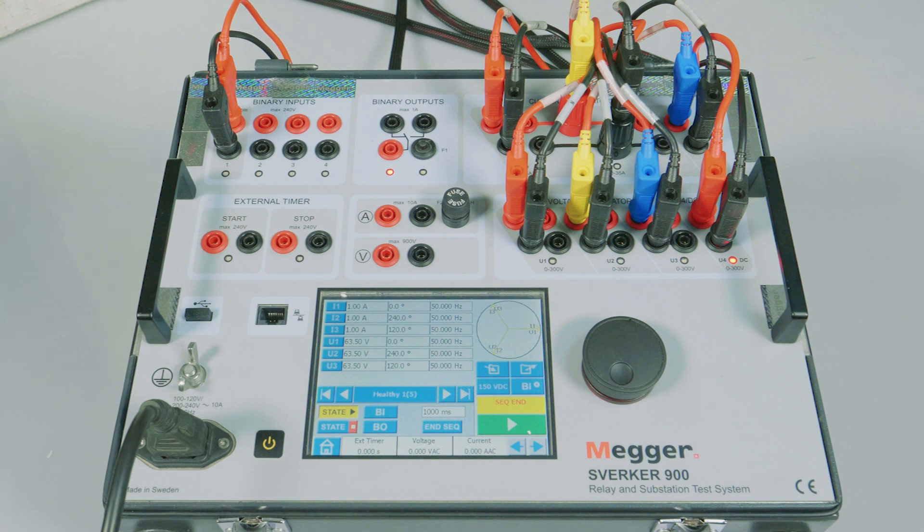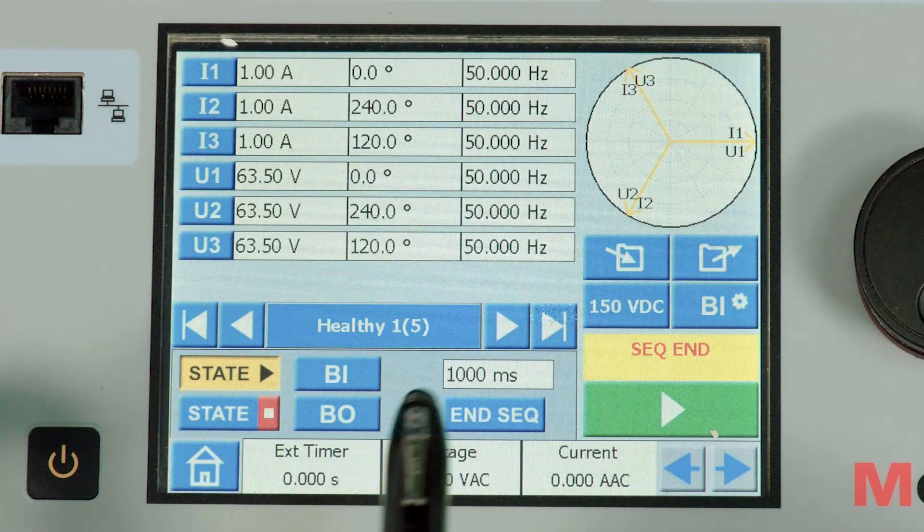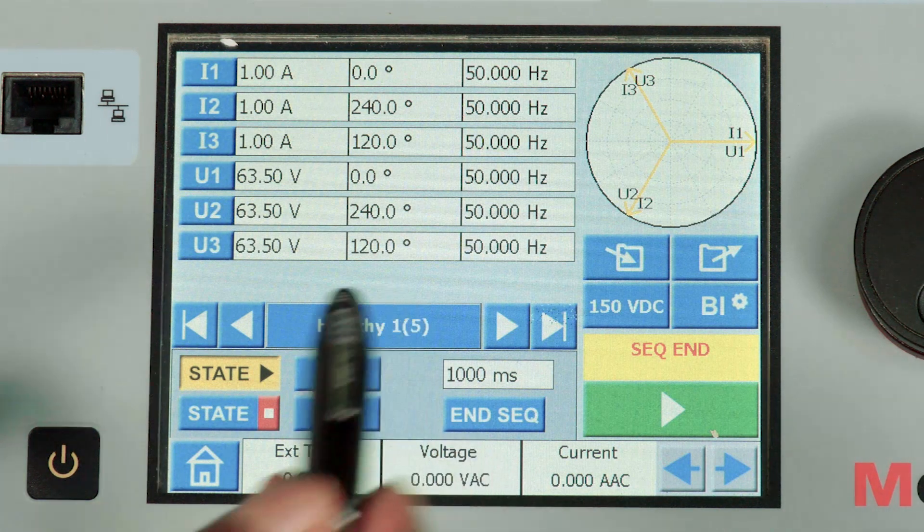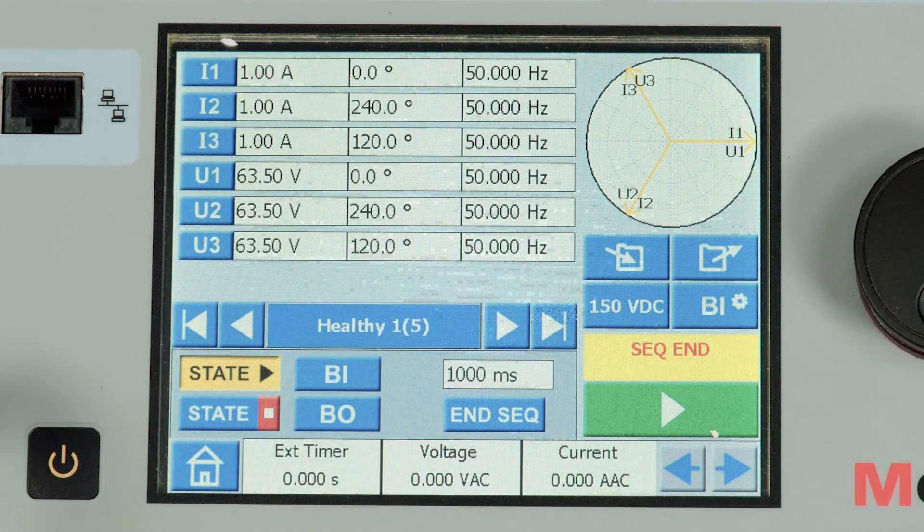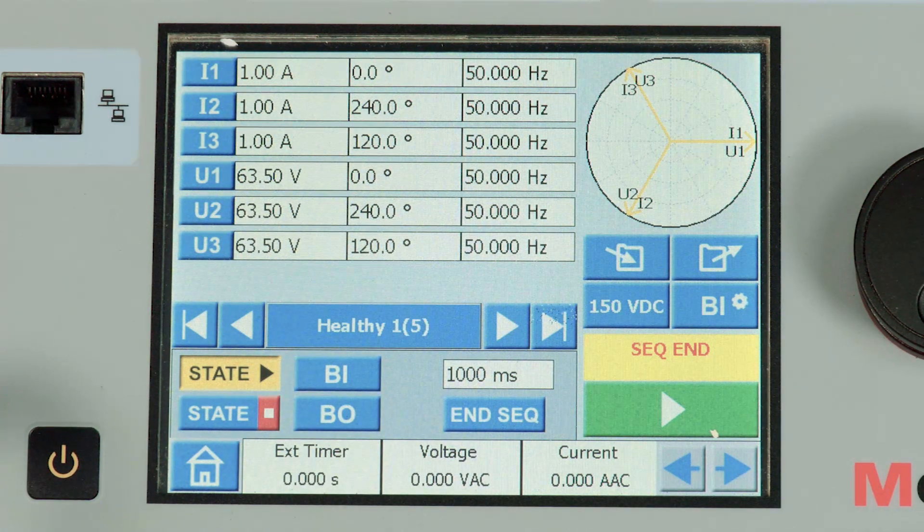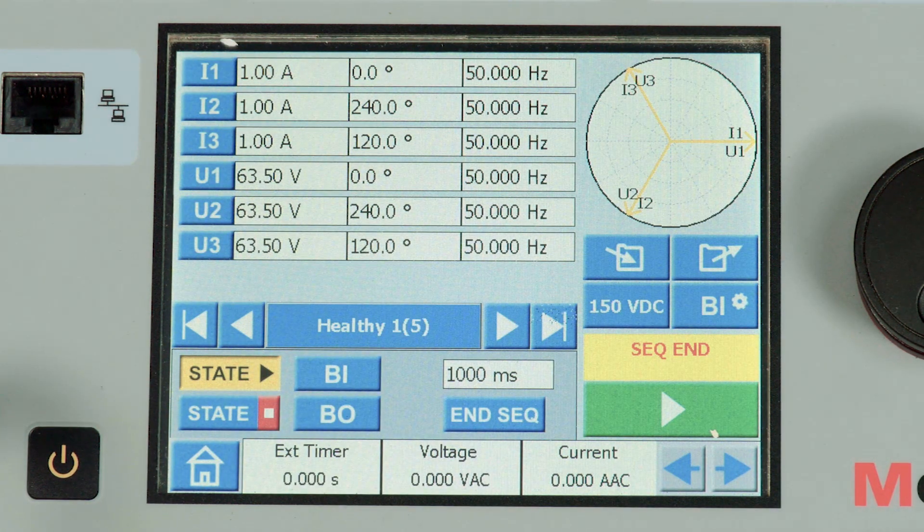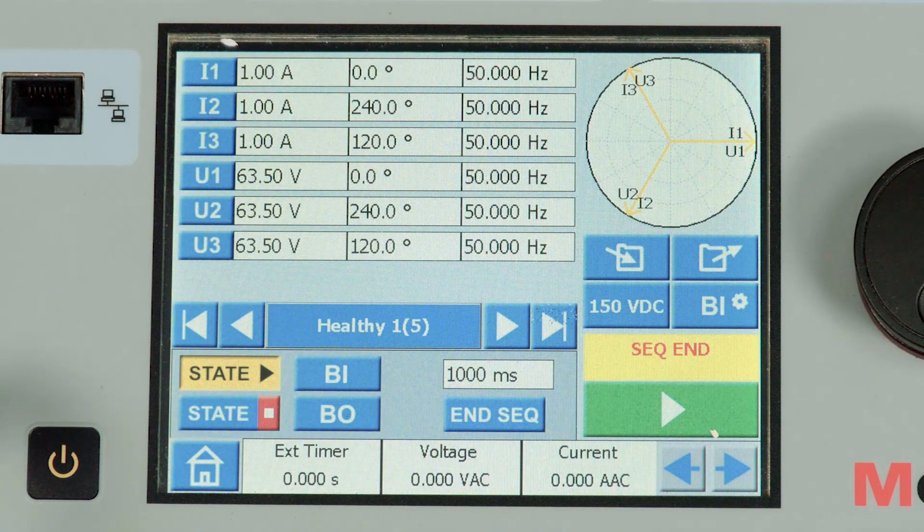This demonstrates an unsuccessful auto recloser where a fault is injected during the reclaim time. State 1 is configured as a healthy state with healthy current and voltage with balanced phase angles for one second.